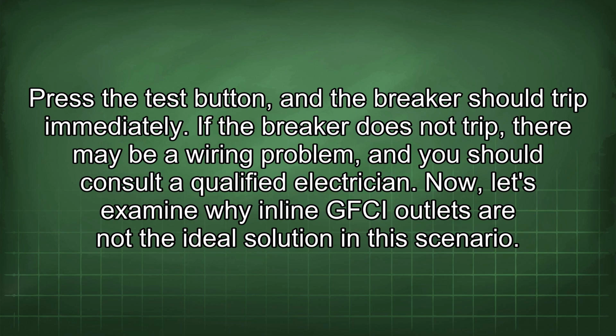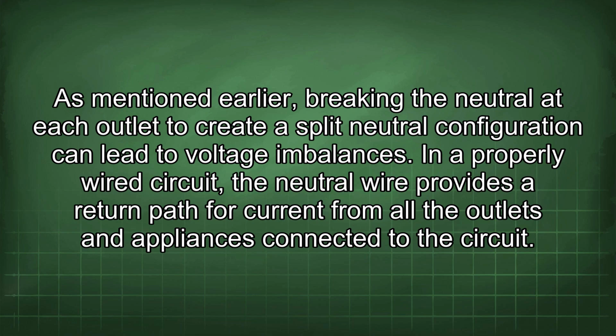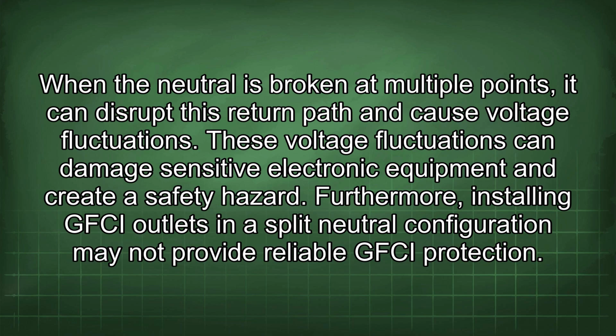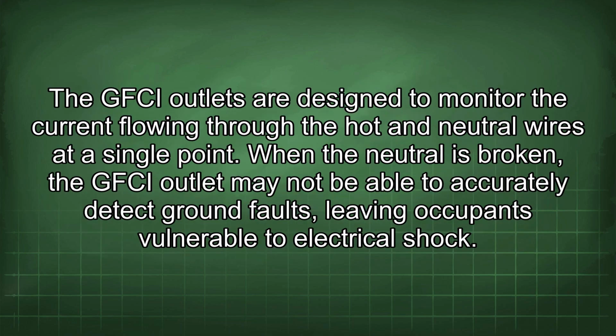Now, let's examine why inline GFCI outlets are not the ideal solution in this scenario. As mentioned earlier, breaking the neutral at each outlet to create a split neutral configuration can lead to voltage imbalances. In a properly wired circuit, the neutral wire provides a return path for current from all the outlets and appliances connected to the circuit. When the neutral is broken at multiple points, it can disrupt this return path and cause voltage fluctuations. These voltage fluctuations can damage sensitive electronic equipment and create a safety hazard. Furthermore, installing GFCI outlets in a split neutral configuration may not provide reliable GFCI protection. The GFCI outlets are designed to monitor the current flowing through the hot and neutral wires at a single point. When the neutral is broken, the GFCI outlet may not be able to accurately detect ground faults, leaving occupants vulnerable to electrical shock.